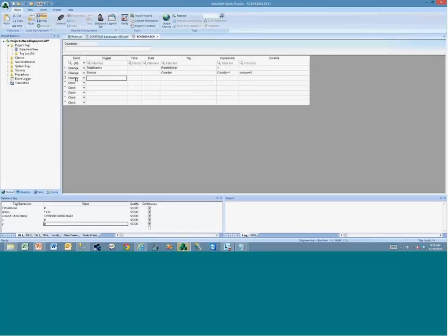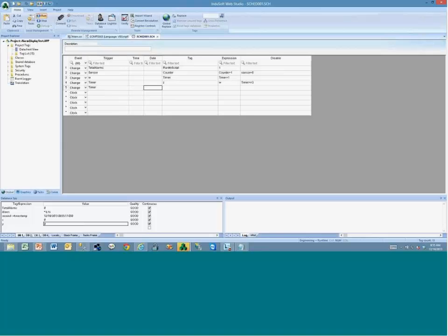So you can say here, change. So when W changes, you have here, let's say, a tag, in this case called timer, but could be any name. So timer is timer plus 1. And every time that the timer changes, you check, you write to Z the value of W, only if timer is greater than or equal to a limit, let's say 3. And every time that the timer changes, timer receives 0 if timer is greater than 3. So those 3 rows make the trick.